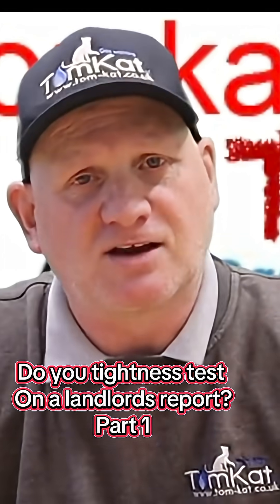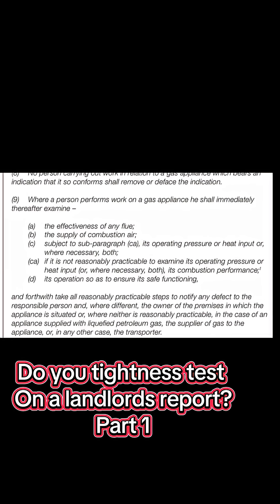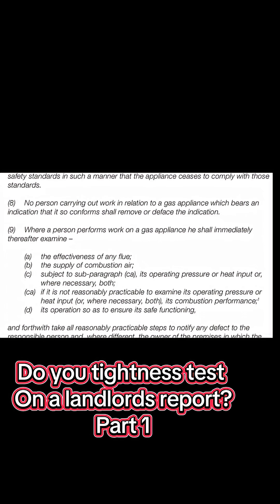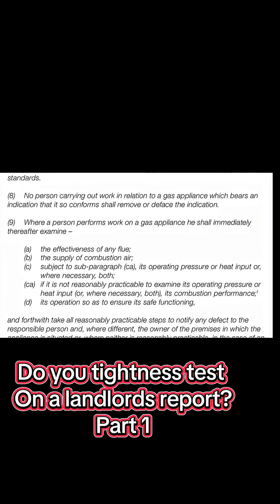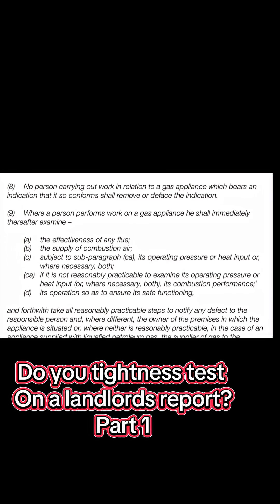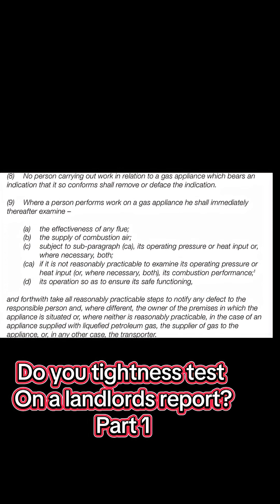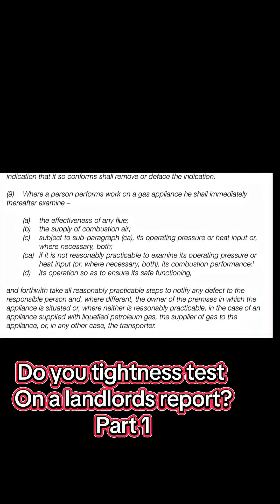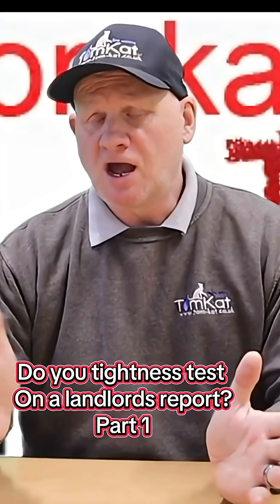Paragraph 9: where a person performs work on a gas appliance, he shall immediately thereafter examine: (a) the effectiveness of any flue, (b) the supply of combustion air, (c) subject to sub-paragraph (ca), its operating pressure or heat input, or when necessary both — or if this is not reasonably practicable, its combustion performance — and (d) its operation, so as to ensure its safe functioning.